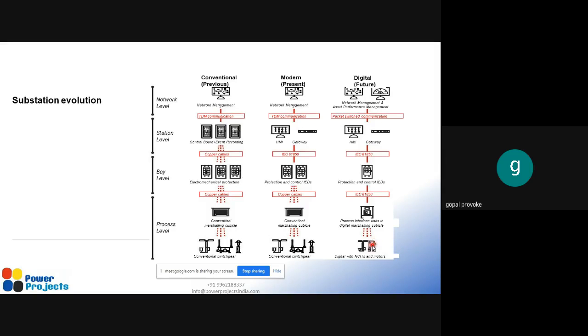These current and voltages will be transmitted to the protection relays in the form of data. But in our present day substation, we are transmitting current and voltages using copper cables, not fiber optic cables, between CT/PT and the protection and control equipment, and this will be sent as a signal.